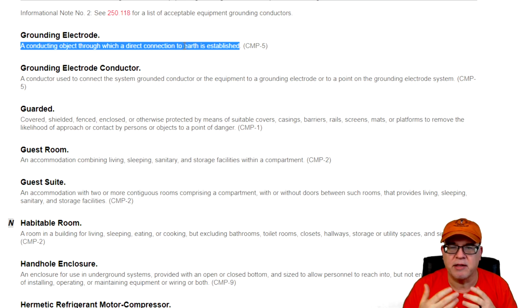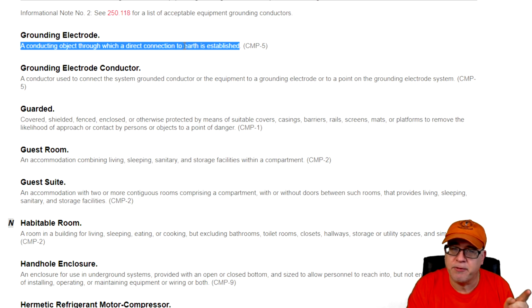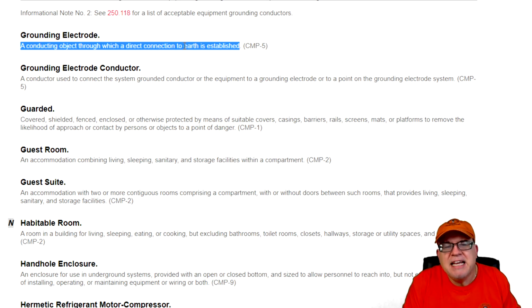Okay, it's an object that we connect to with the grounding electrode conductor in order to make that intimate connection with earth. Same with a concrete encased electrode. That's a grounding electrode. A water pipe ground that's in the earth, it's metal, it's 10 foot in contact with the earth, where you have one, very rare today, that is a grounding electrode. So we have a list of grounding electrodes in 250.52, and that tells you all of them. And so those are making a direct, intimate contact connection to earth, like a ground ring makes connection into the earth, okay? And of course, we'll cover all those electrodes when we get there.